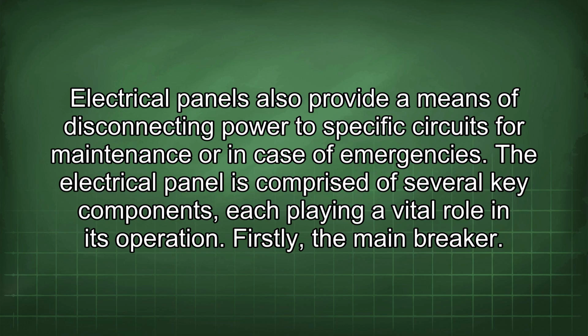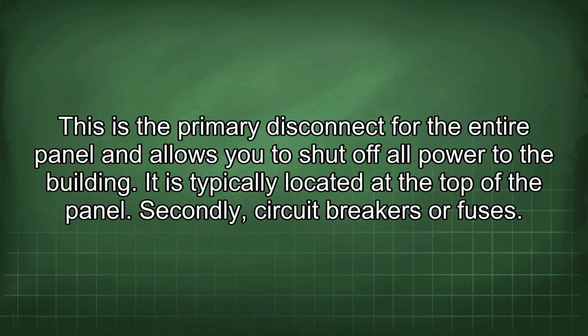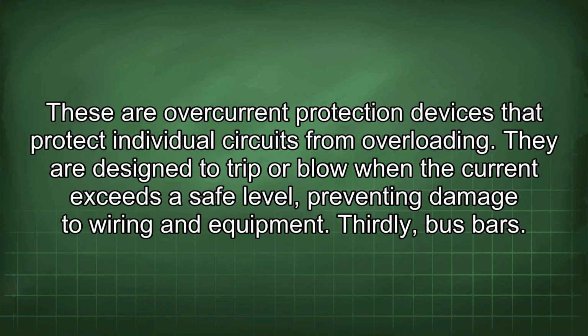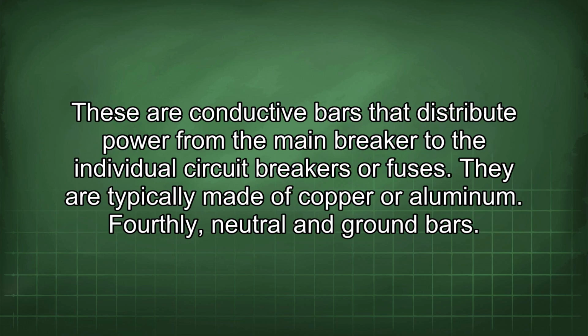Firstly, the main breaker. This is the primary disconnect for the entire panel and allows you to shut off all power to the building. It is typically located at the top of the panel. Secondly, circuit breakers or fuses. These are overcurrent protection devices that protect individual circuits from overloading. They are designed to trip or blow when the current exceeds a safe level, preventing damage to wiring and equipment. Thirdly, bus bars. These are conductive bars that distribute power from the main breaker to the individual circuit breakers or fuses. They are typically made of copper or aluminum.